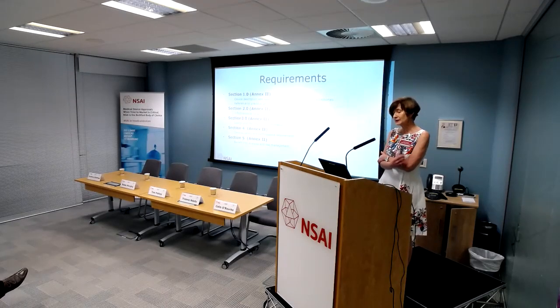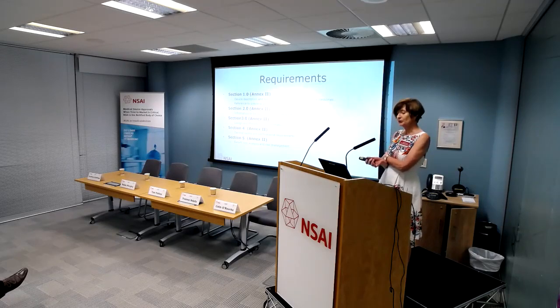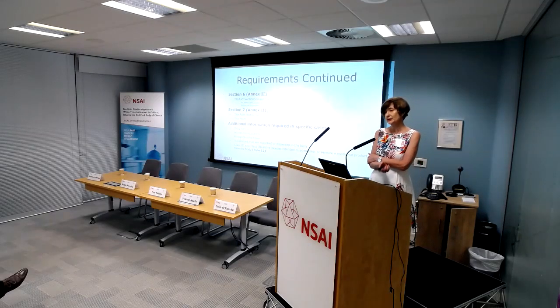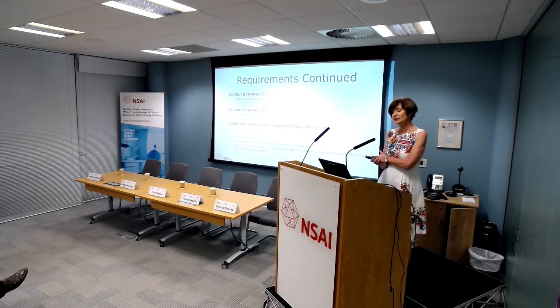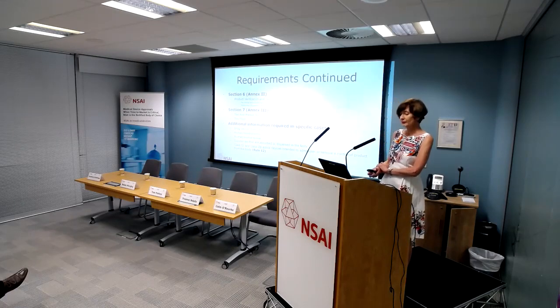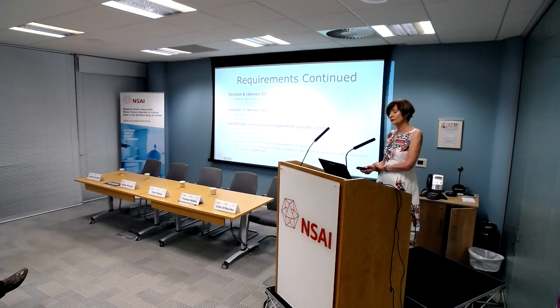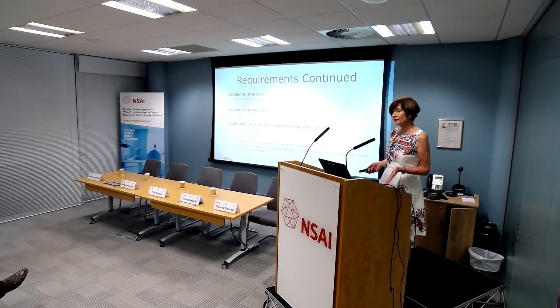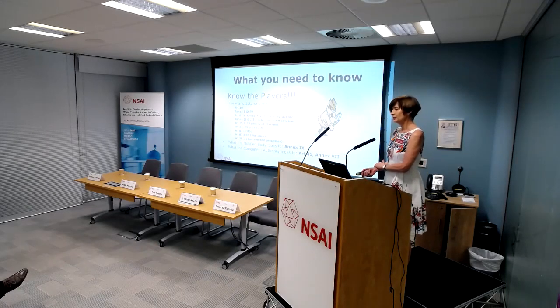So the elements that tell you how to produce your technical documentation are defined in Annex 2 and Annex 3 of the regulation. Section 1 talks about the description. Section 2 is the information, 3 design, 4 general safety, 5 risk benefit, 6 verification validation. Section 7 then is your PMS, which is Annex 3. And then depending on the product, there are specific requirements. You might have a drug device combination, you might have human blood plasma, human or animal tissue, or class 3 or class 2B devices intended to administer or remove a medicinal product from the body. So there are differences, but as I say, it's prescriptive. The rules are there, just follow the rules and you'll know where you go.